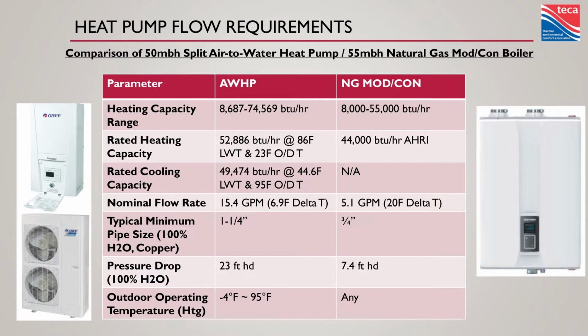It goes anywhere from 8,600 BTUs to almost 75,000. Now that's not at the times when I need that 75,000. That's at the time that I don't know what to do with that 75,000, when it's mild out. But it's rated at 52,886 with an 86 degree leaving water temperature when it's 23 Fahrenheit outside. So we can only really pick a set of numbers to give it a number, but that's the range. Meanwhile, we've got a gas boiler that gives us between 8,000 and 55,000 regardless of the weather. So we need to start thinking about things like balance point charts when we're sizing our equipment. I've got some slides to show you what that means.